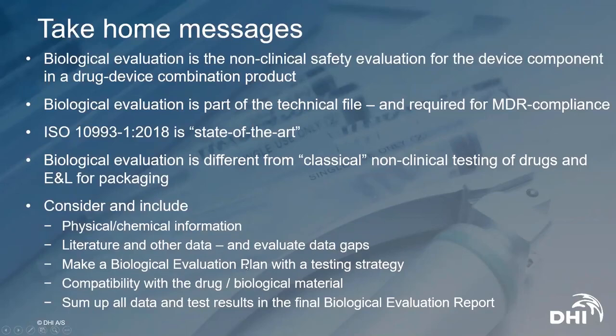You should make a biological evaluation plan when you have summed up the available information and then perform your testing strategy. When you do your testing strategy, you may also want to consider, is there something on the compatibility between the drug and the biological material and the materials in your device? And you should sum up all the data and test results in the final biological evaluation report.